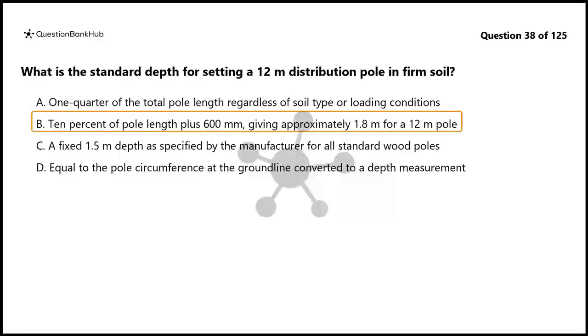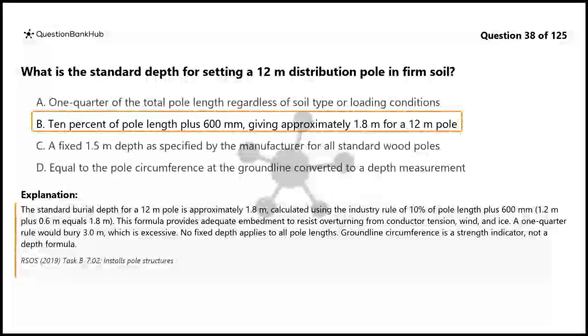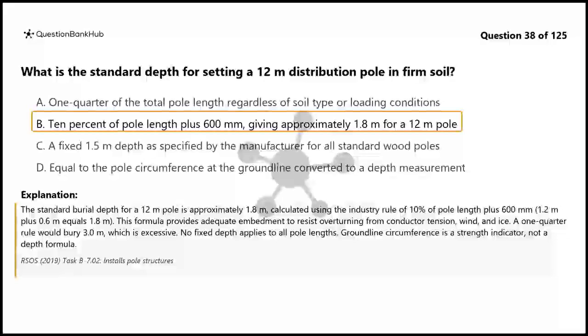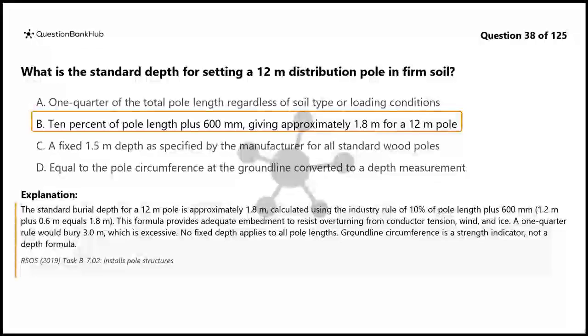The correct answer is B. The standard burial depth for a 12 meters pole is approximately 1.8 meters, calculated using the industry rule of 10% of pole length plus 600 mm, 1.2 meters plus 0.6 meters equals 1.8 meters. This formula provides adequate embedment to resist overturning from conductor tension, wind, and ice. A 1/4 rule would bury 3.0 meters, which is excessive. No fixed depth applies to all pole lengths. Ground line circumference is a strength indicator, not a depth formula.